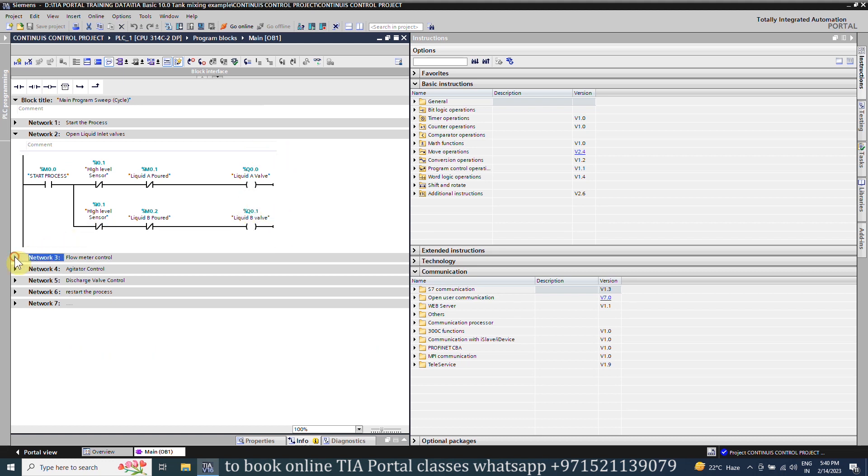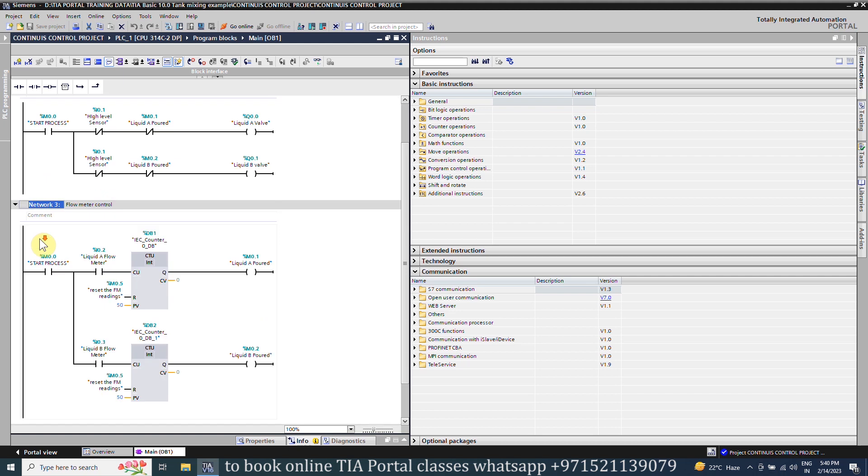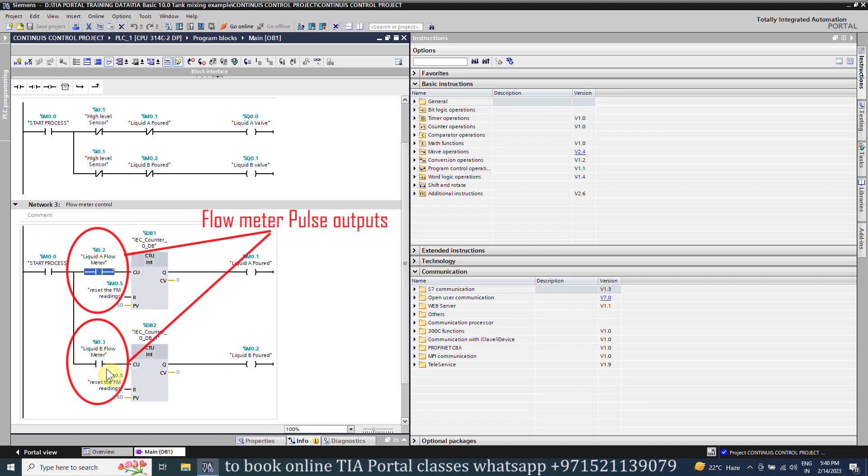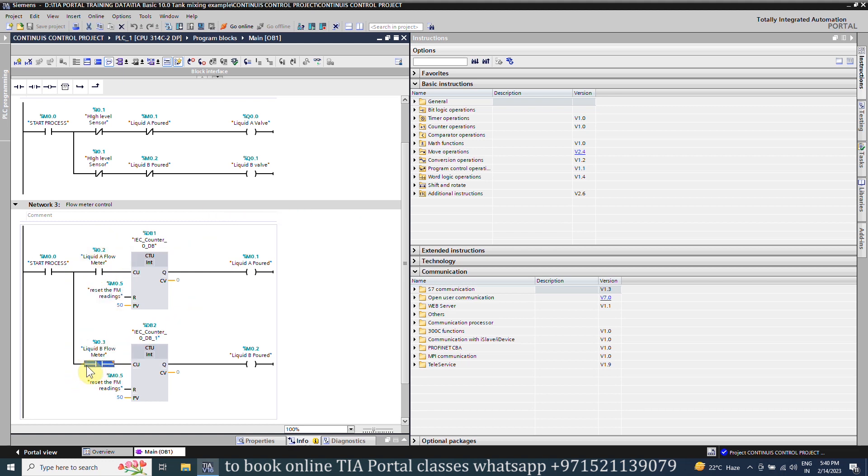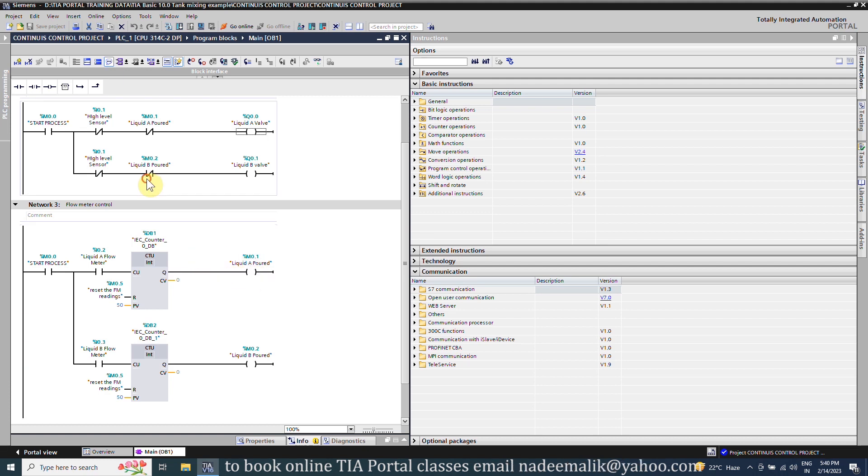In network number three we have written the logic to measure the flow of the water. As the inlet valves open these flow meters output pulses, we can count these pulses to measure the liquid using counters. As the 50 liters liquid flow through these flow meters M0.2 and M0.1 turn on to confirm that required 50 liters of liquid from both lines A and B is poured into the tank. And these two bits will turn off the inlet valves A and B.